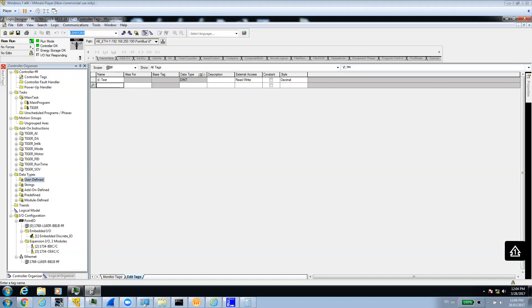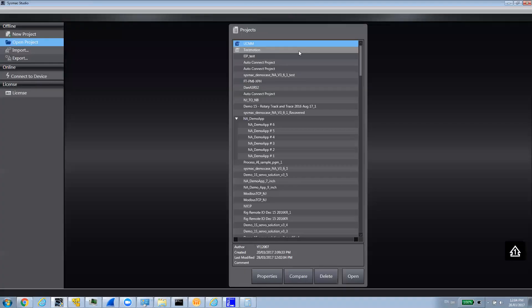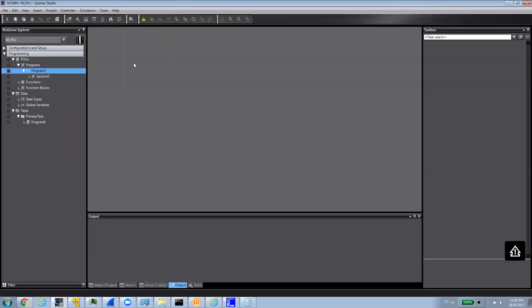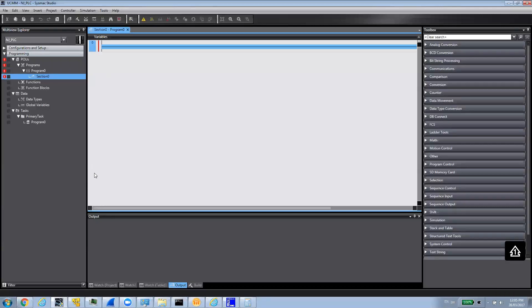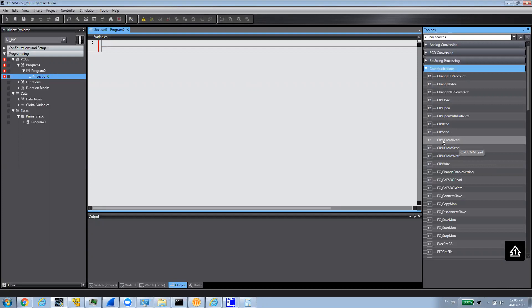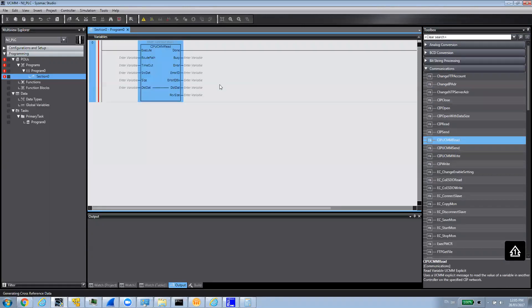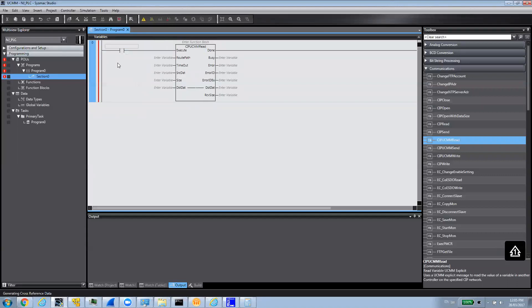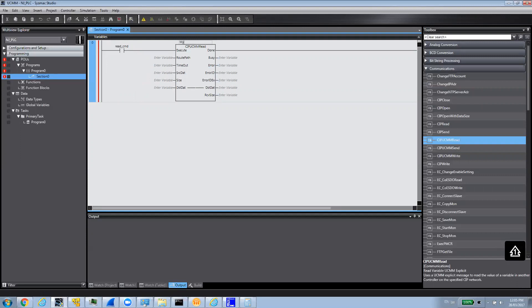Now, on the NJ side, I'm going to open this project. Right now, in this PLC, I'm going to open up a section. I have nothing right now. I'm going to create a couple rungs to be able to read from the Compact Logix and write to it. The functions I'm going to be using is the CIP class 3 functions. I'm going to use CIP read for reading. I'm just going to create here a contact. I'm going to call this read command. And then, I'm going to give my function block instance a name. I'm going to call it my read CIP.